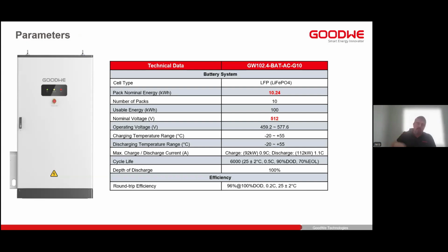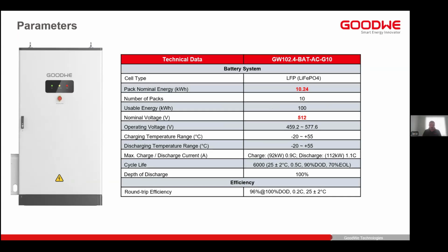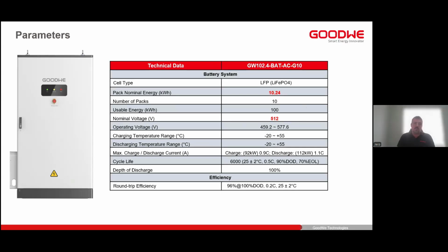Taking a quick look at the technical specs, the nominal pack energy per pack is 10.24 kilowatt hours. There's 10 packs in one storage solution, and the usable energy is then 100 kilowatt hours. The pack voltage is 512 volt, and the operating voltage is from 459 to 577 volts. Cycle life is rated at 6,000 cycles, with 90% DoD at 70% end of life. Supported depth of discharge is 100%, although by default, the GoodWe ET50 inverter will not allow you to discharge more than 95%. To achieve that, we need to do a special command, because that 5% is purely there to protect the battery.